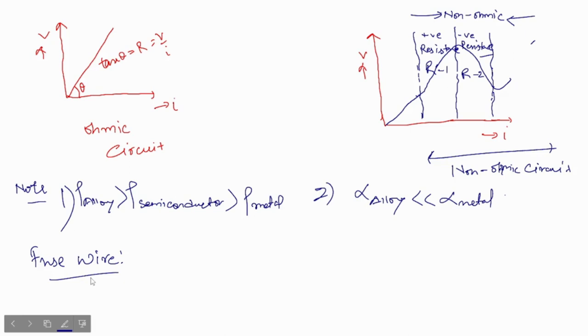Basically, what happens is that when there is some kind of short circuit in the electric circuit, this wire, having a low melting point, will be affected. So what will happen when there is a short circuit? There will be a heating effect of electric current. So this fuse wire actually melts and breaks the connection from where the fault has happened to the whole circuit of the house, or you can say at some other places, so that there will not be any flow of current.